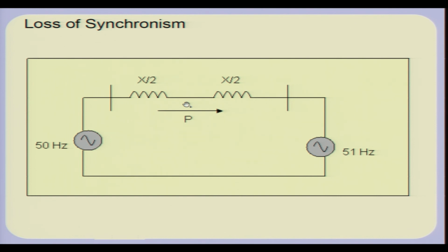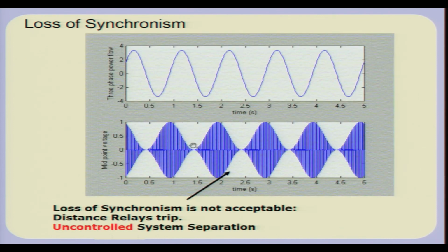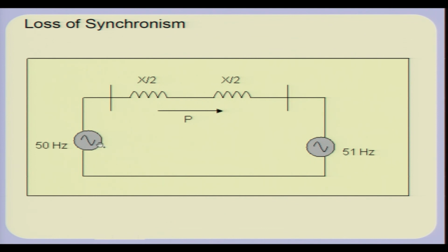So, in case loss of synchronism occurs and at some point in the transmission system the voltages oscillate the way I have shown you here, then usually some relays pick it up and trip. Inadvertent means it is not intentional, but they trip and the system separates into two parts, which is just as well, because you can't operate this way. Okay. This is of course only a thought experiment where a machine of 50 hertz is connected to another machine at 51 hertz, and we just solve this circuit.